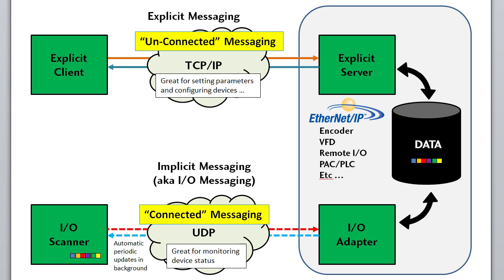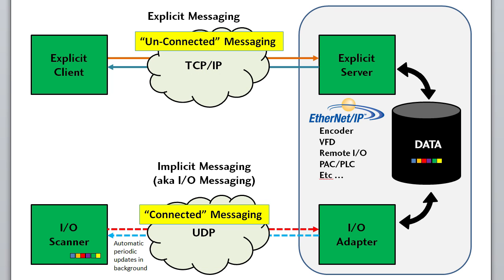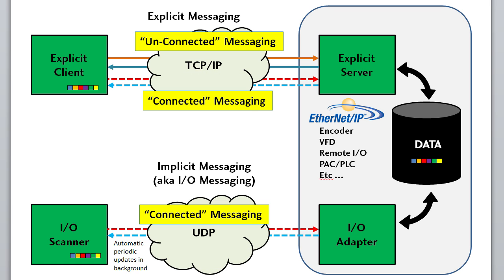The explicit protocol can also do connected messaging, where both ends know exactly what to expect and the data is transferred at periodic intervals in the background. But it still uses TCP/IP with all that extra communications baggage built into the message, so it's not nearly as efficient as the implicit version of connected messaging — but it is available for you to use if you want.